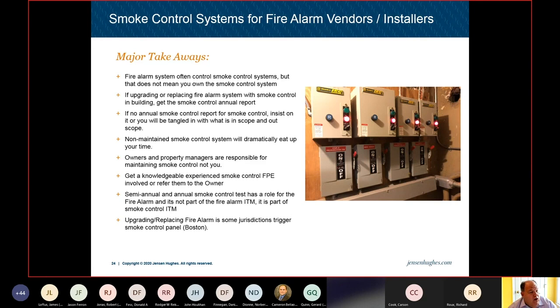And then you do have to watch out when you start upgrading and replacing fire alarm systems that do control smoke control systems. In some jurisdictions, that triggers a smoke control panel, i.e. Boston. So in Boston, if you're putting in a new fire alarm panel, either as a new system or a panel upgrade, they're looking for a smoke control panel, and having someone who understands what that all means helps. You're not trying to do everything like new, but there are some things that can get negotiated with Boston as part of that.